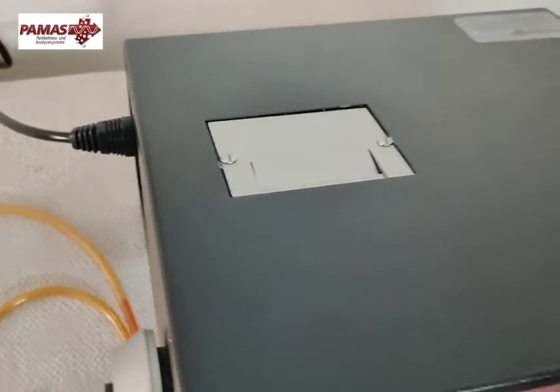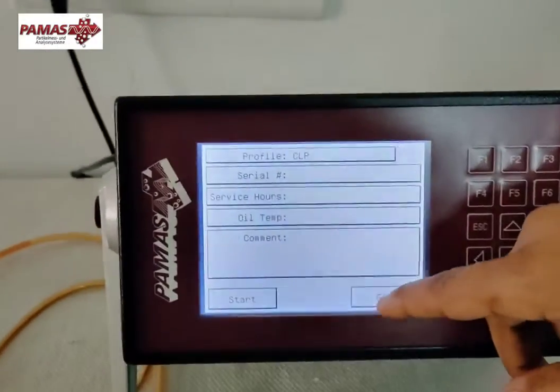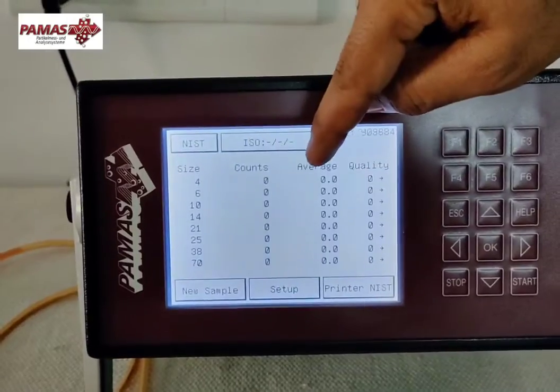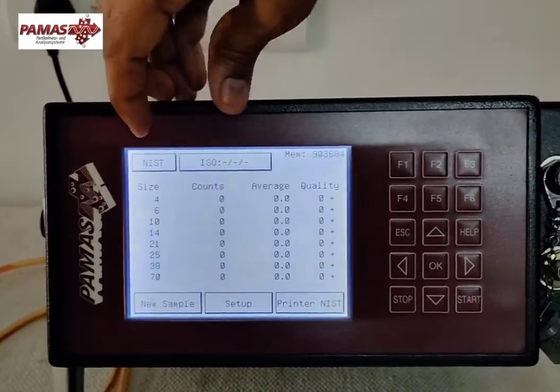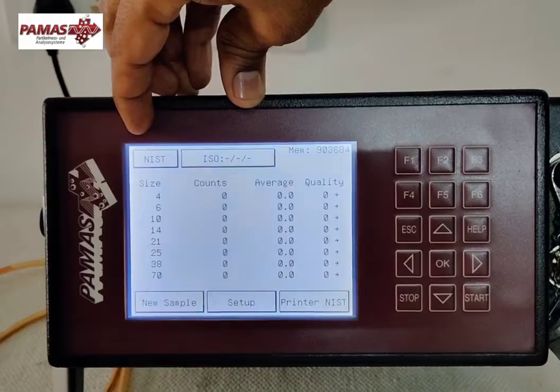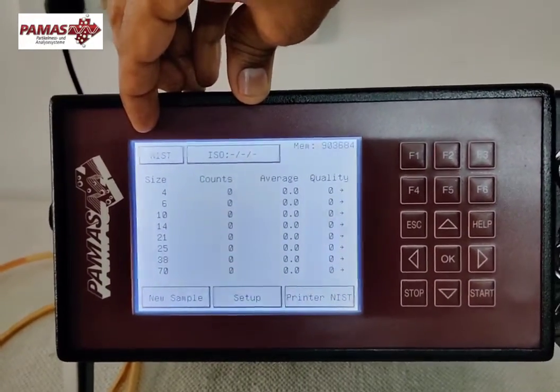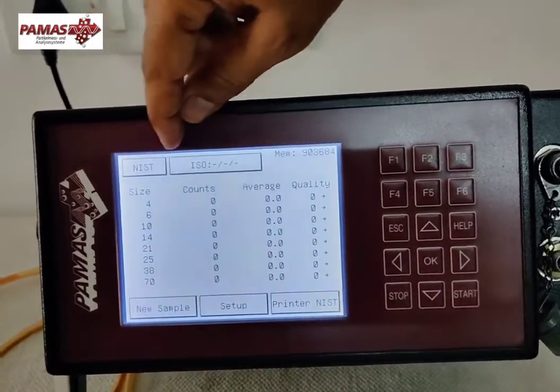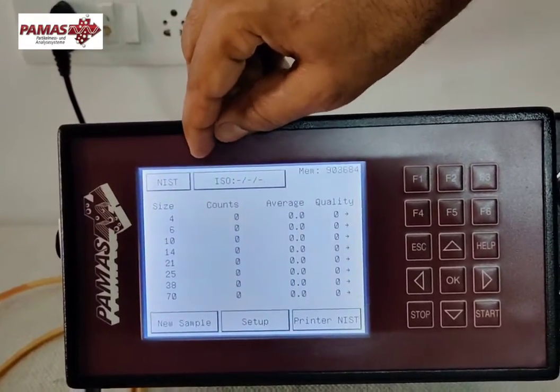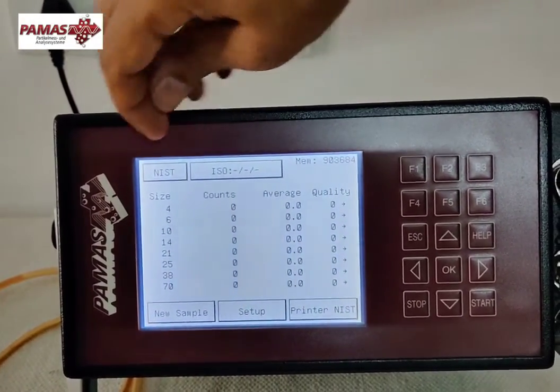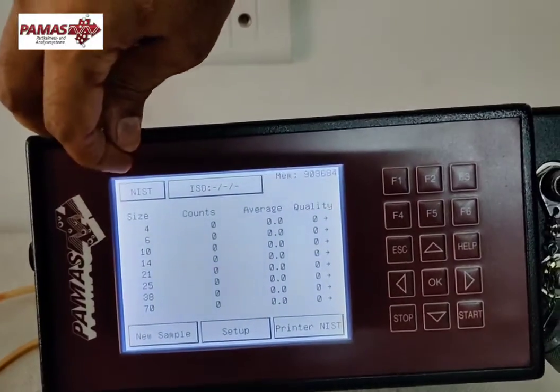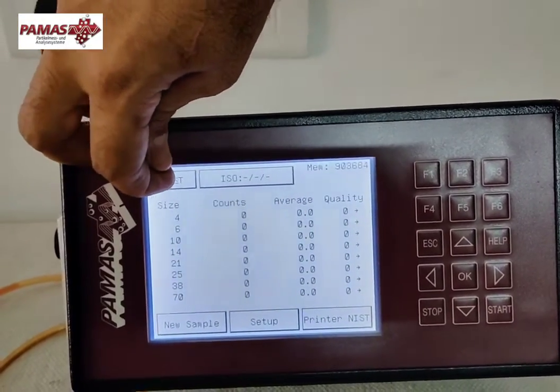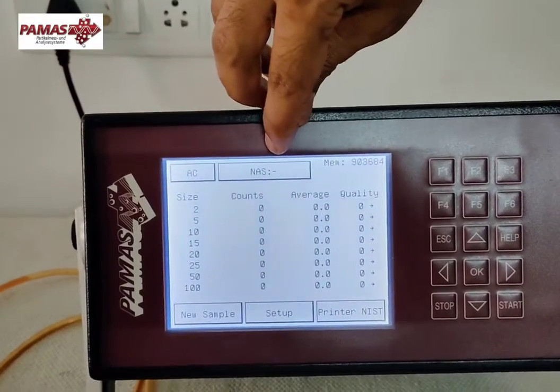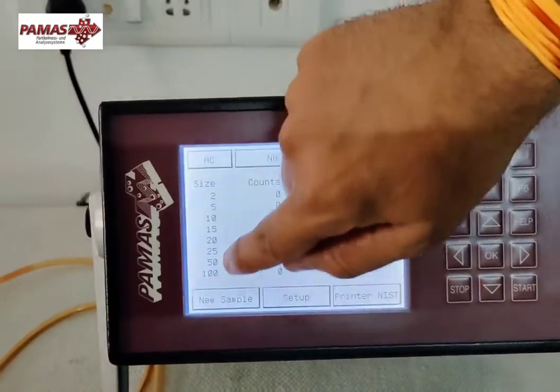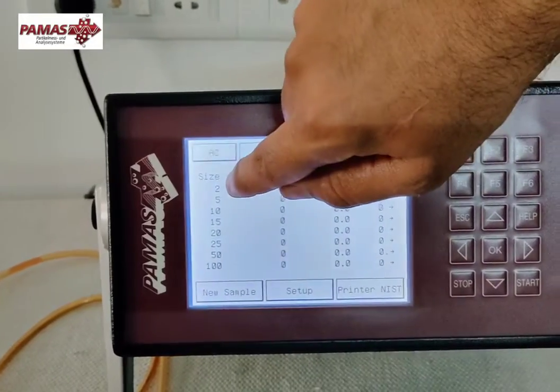And this is the touch screen here. And you can see this is the home screen here. So now, for example, I'm following the ISO 11171 calibration and I just need readings in ISO. So I will simply use this particular screen. And if I want to make measurement in AC, which is NAS calibration, I just have to change it to AC, and now I will get the NAS. Here you can see the particle range is different in NAS, and in ISO it's different.